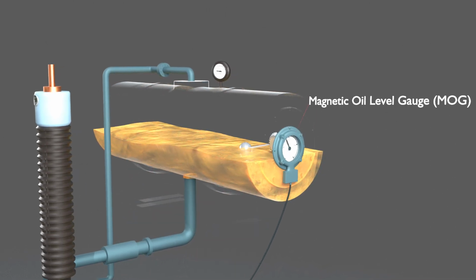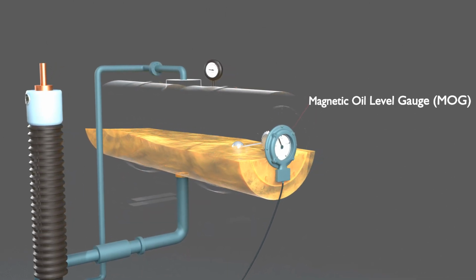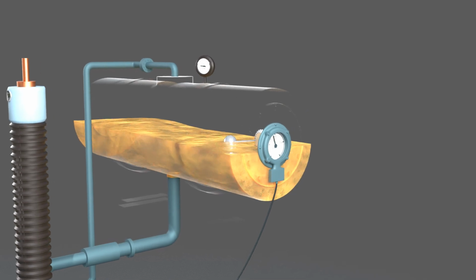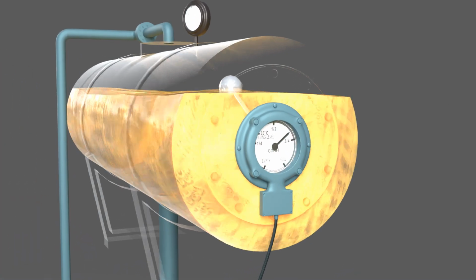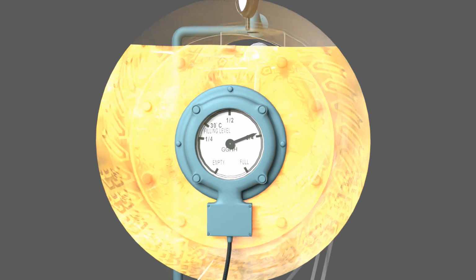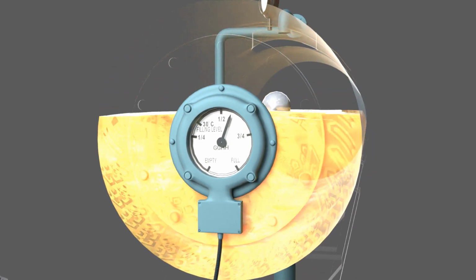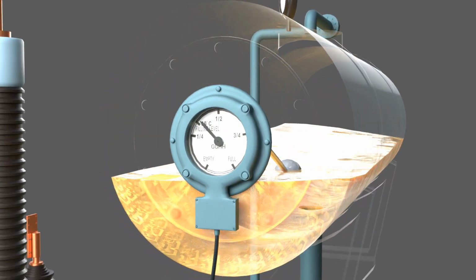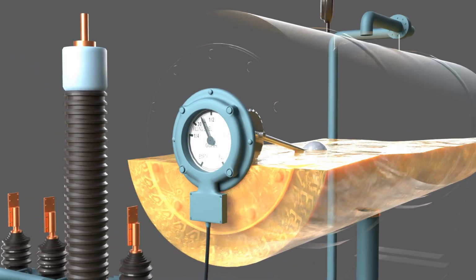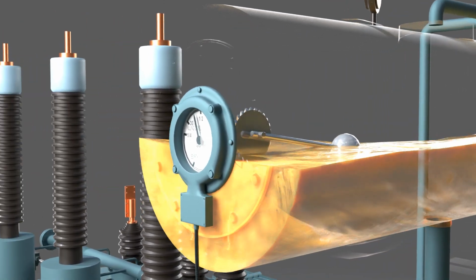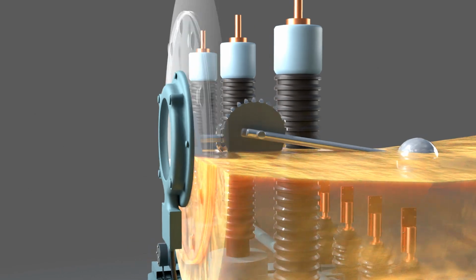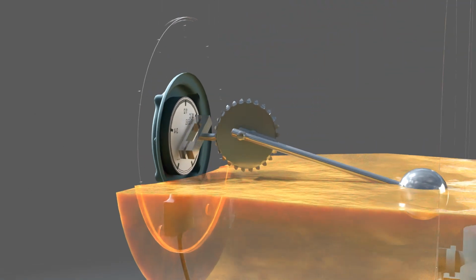The magnetic oil gauge, or MOG, in a power transformer monitors the oil level inside the tank using a float mechanism. As the oil level changes, the float moves up or down, causing a magnetic coupling to rotate the indicator needle on the dial gauge. This movement provides real-time oil level readings, and triggers an alarm if the level drops critically, ensuring safe and efficient transformer operation.